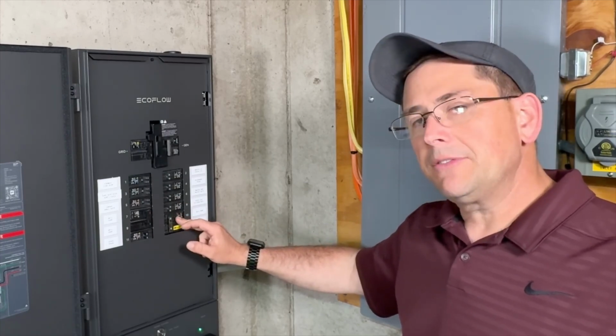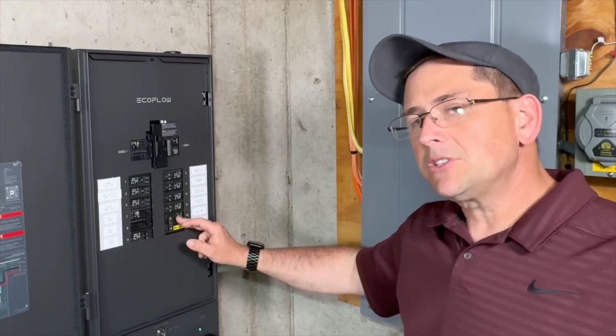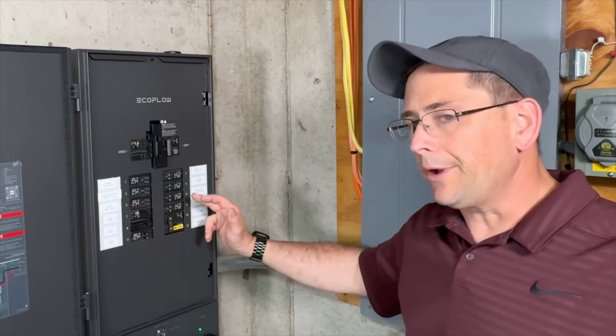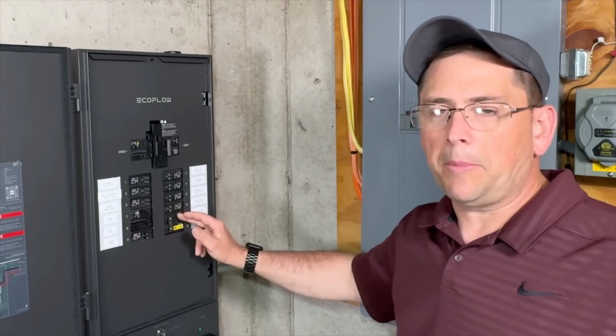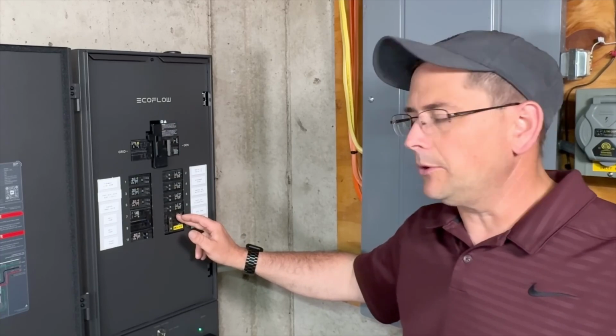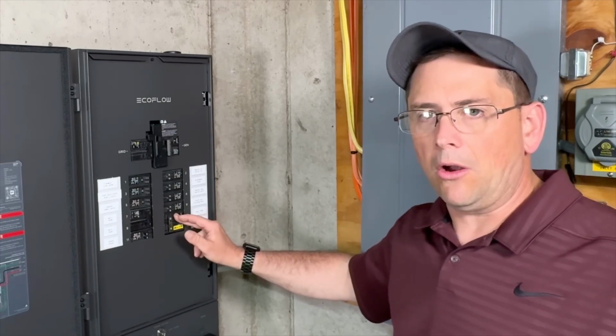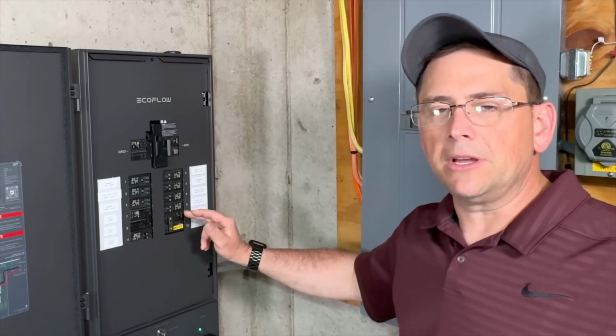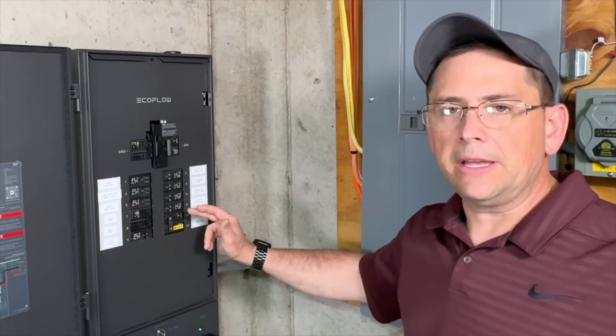Now, this is a 2.5 ton heat pump. This inverter system is rated for up to a 3-ton air conditioner or heat pump. The way they are rating this maximum capacity of what kind of unit it can run, they're doing it off the locked rotor amps, LRA. If it has a locked rotor amps under 120 amps, then they say it can run it.